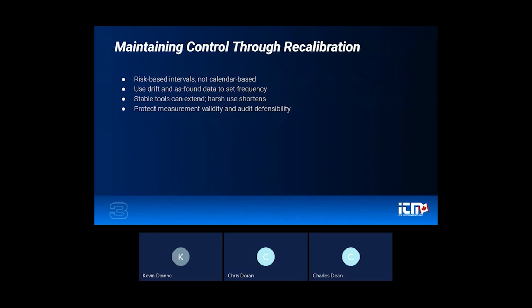As a final point here, just to address recalibration and how calibration intervals are managed over time. In many pressure applications, 6 to 12 months is a baseline. However, like I said, your recalibration should really be risk-based, application-based, not a fixed calendar assumption. In practice, recalibration decisions should be informed by historical calibration results, particularly your as-found data and your observed drift over time. Instruments that demonstrate stable, repeatable performance may justify extending those intervals, while instruments that are exposed to higher stress, harsh environments, and continuously don't meet those intervals, you should probably be recalibrating more often.